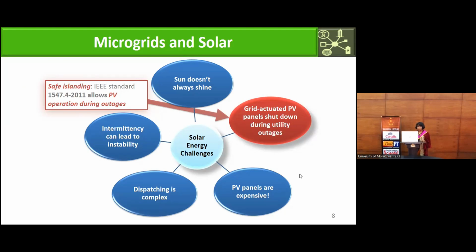So the previous IEEE 1547 standard was specifying to trip off these distributed generators, the generators connected to the distribution system, within 2 seconds if the grid is not available. That is actually for security and protection requirements, because the dispatcher doesn't know whether these generator stations are there or not. So that is for security.